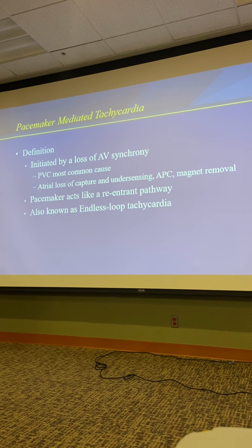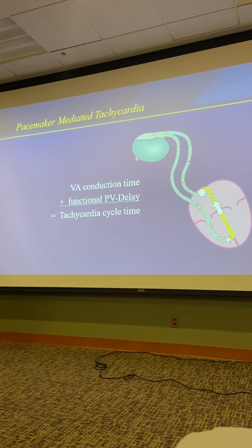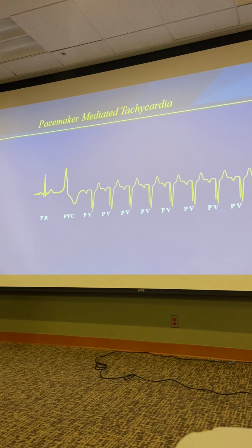And then you set up a circuit where the signal arose from the ventricle and went backwards. It was sensed as a P wave. The pacemaker quickly tells the ventricle to fire again. That signal continues to go backwards, tells the pacemaker to fire, and it goes very rapidly. And this is what you'll typically see: some sort of normal rhythm, whether it's paced or intrinsic, a P wave. That P wave travels the wrong way, and it sets up this circuit.